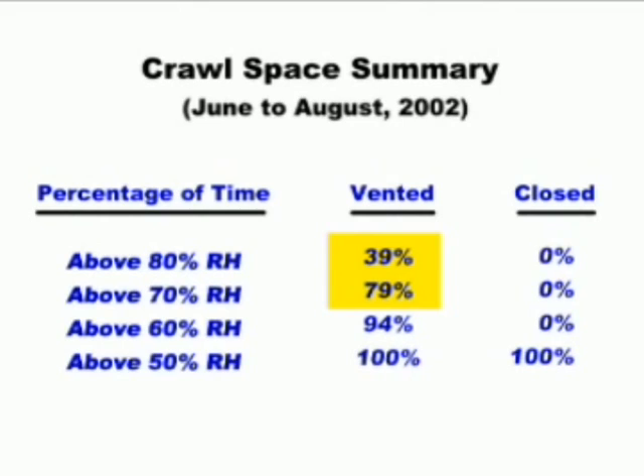From June to August 2002, the wall-vented crawlspaces stayed above 70% relative humidity 79% of the time, and they stayed above 80% relative humidity 39% of the time. While the closed crawlspaces never got above 60% relative humidity.